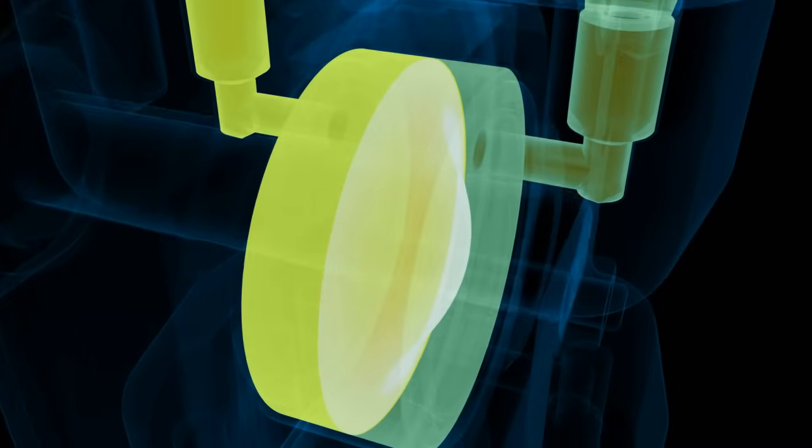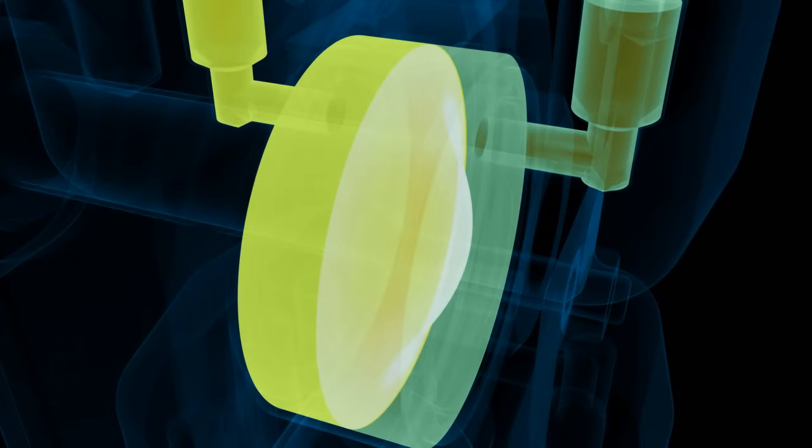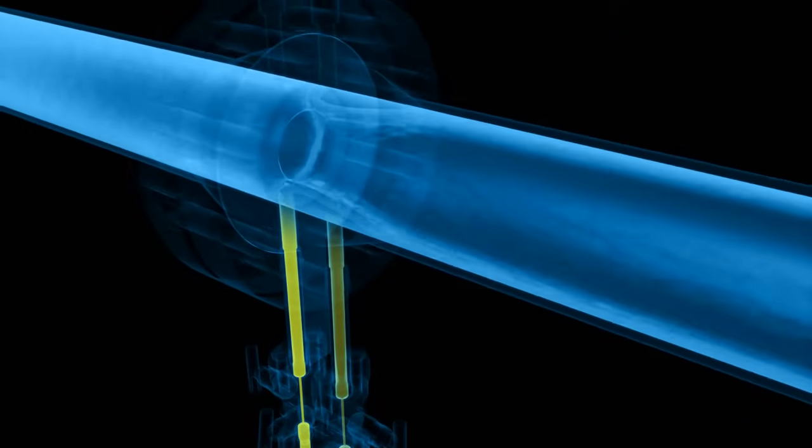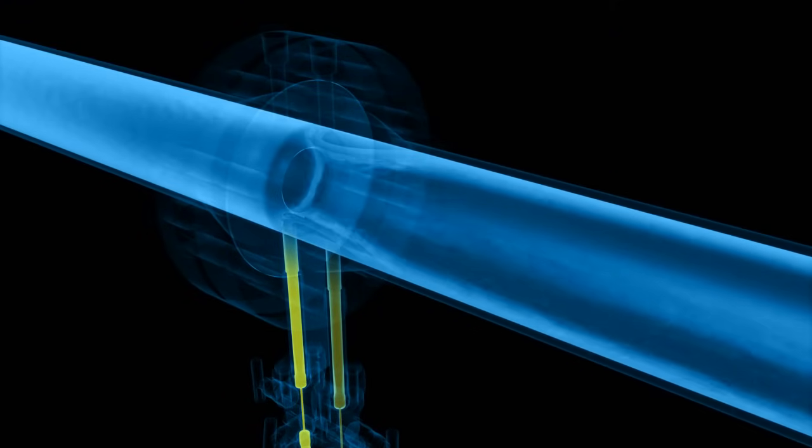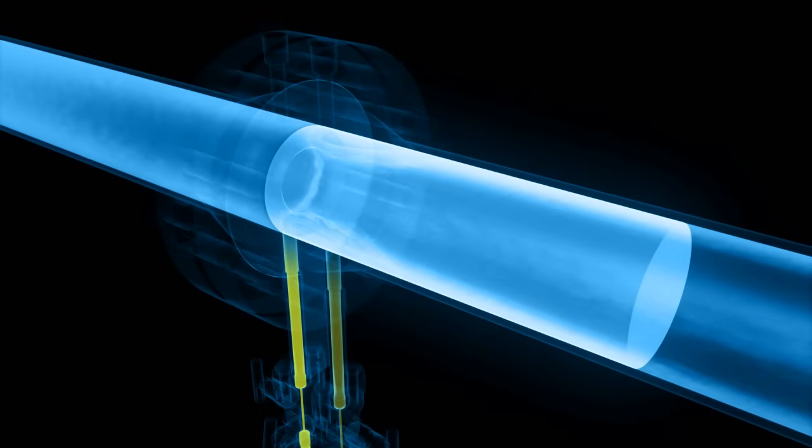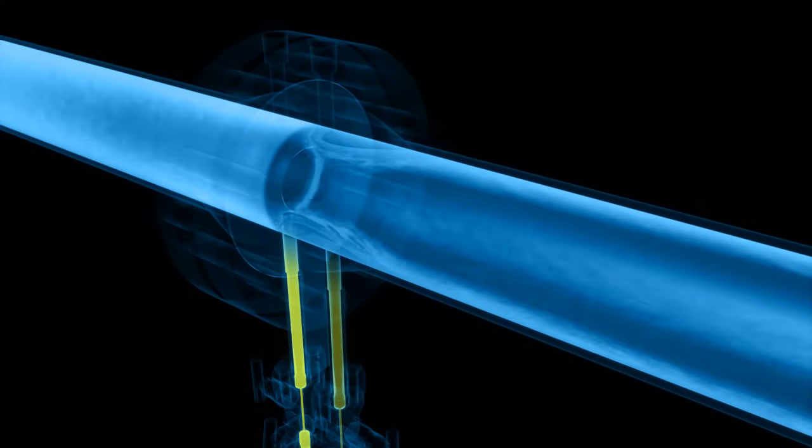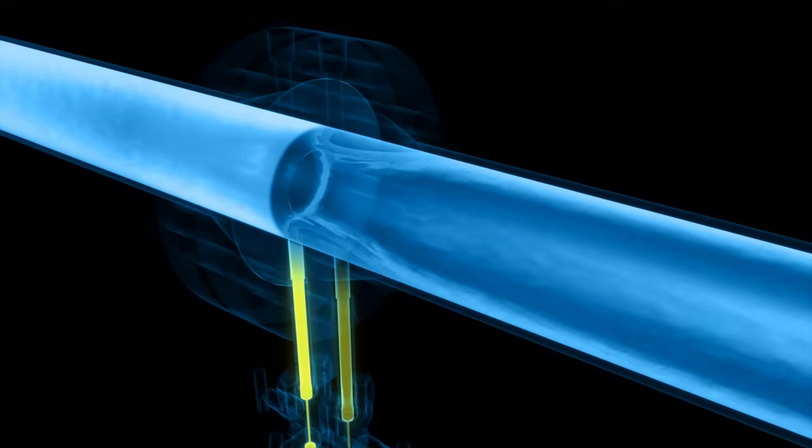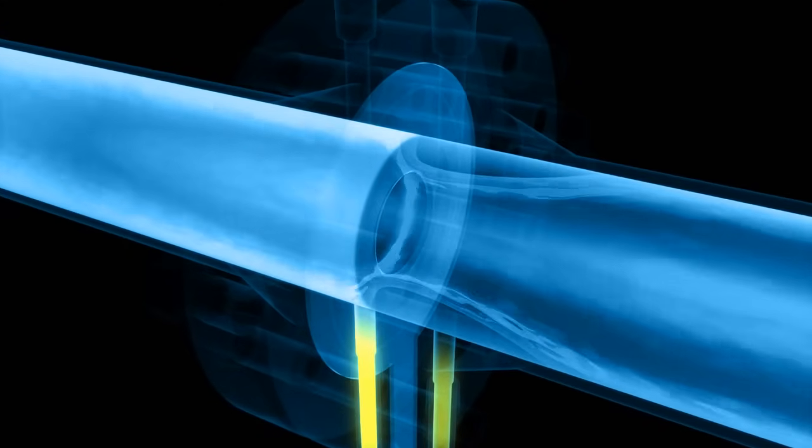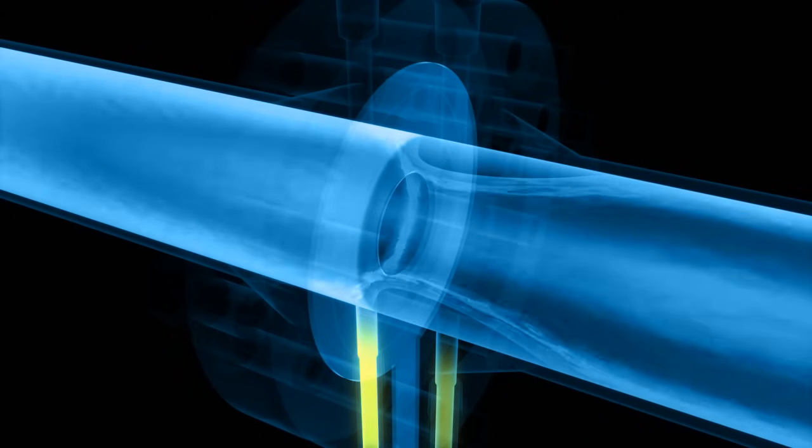Consequently, different values are detected in the pressure chambers of the sensor, a higher pressure before and a lower pressure after the orifice plate. This pressure difference is a direct measure for the flow velocity and thus the mass and volume flow in the pipe. The higher the flow velocity and the resulting drop in pressure around the orifice plate, the greater the differential pressure measured.